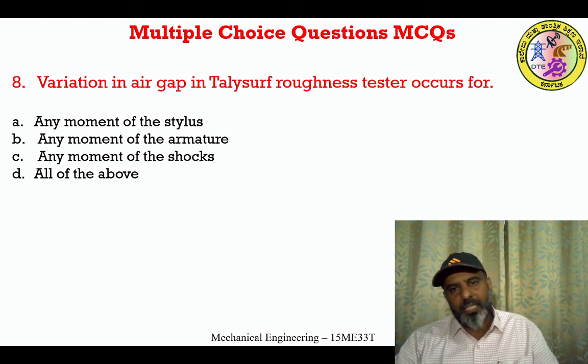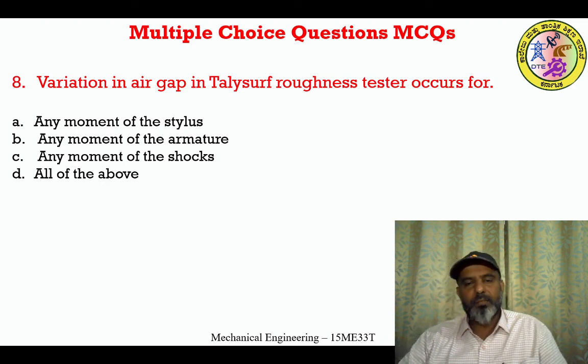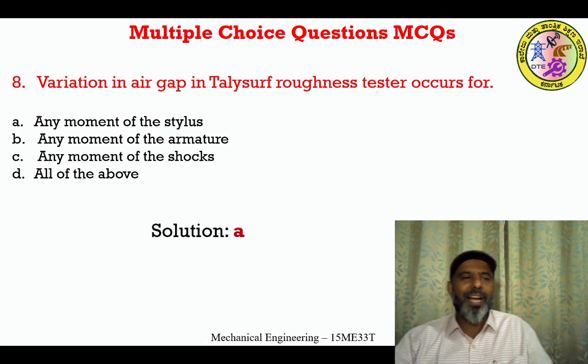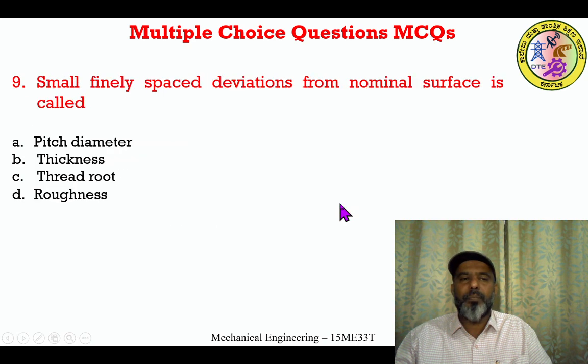You should answer this. The answer is A. Any movement of the stylus is the correct answer. Any movement of the stylus creates variation in the air gap.